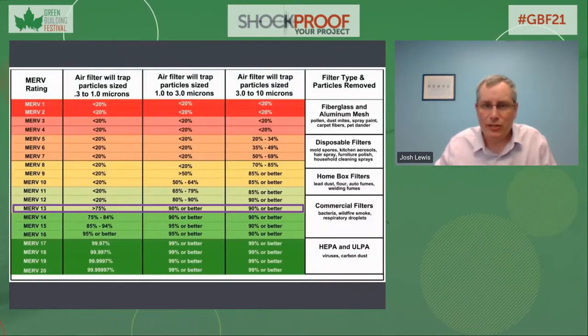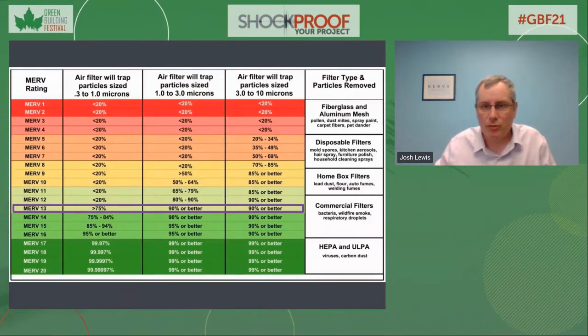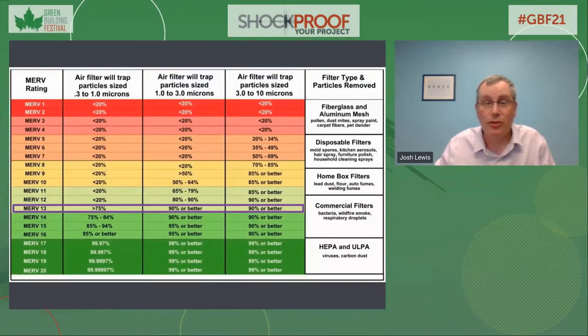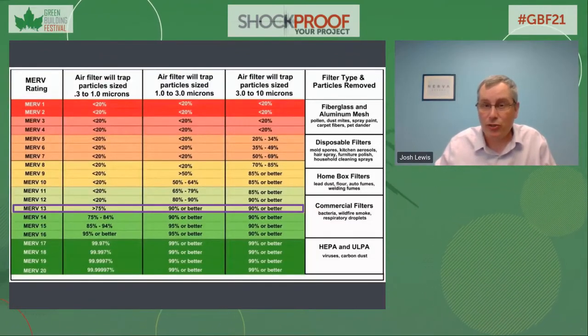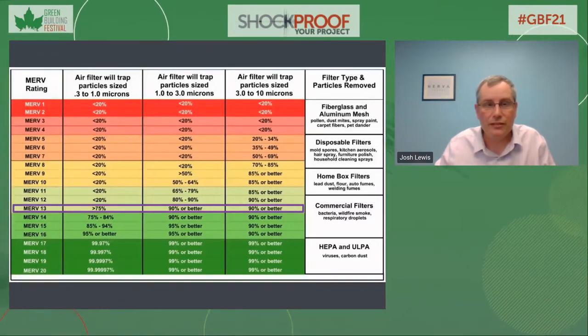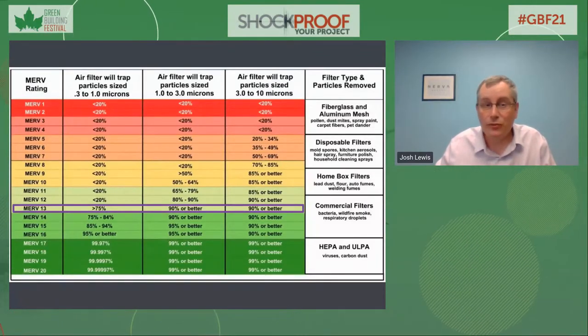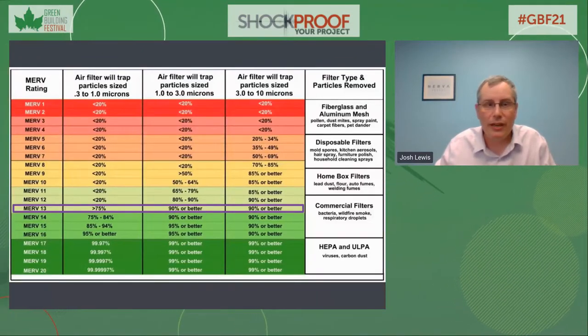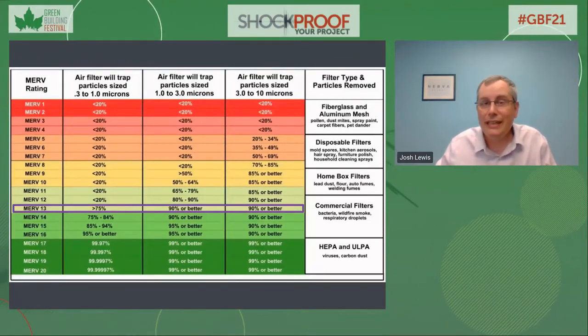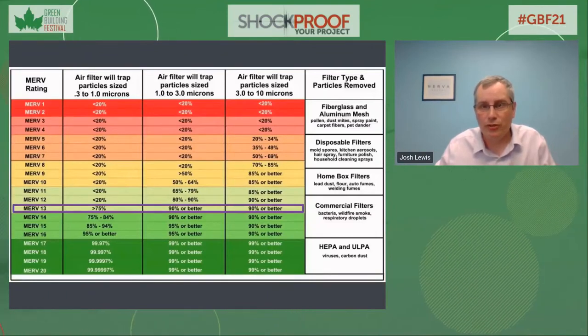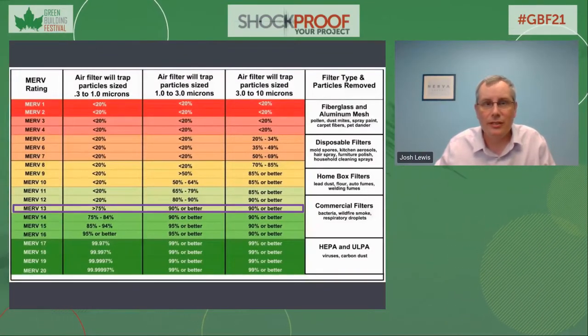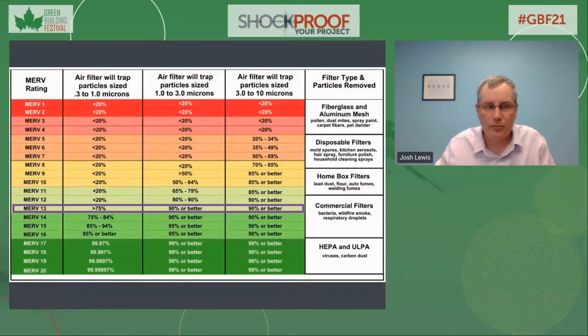The impact of both of these concerns can be minimized by using a measurement, specifically the differential pressure drop across the filter. The amount of pressure lost across the filter provides a clear indication of how dirty the filter is, and also how much impact it's having on the amount of energy the fan is using to move the air. The most energy efficient, cost-effective, and environmentally sustainable way to decide when to change a filter is to measure and monitor the differential pressure across it, then swap it out when it hits the manufacturer's recommended pressure value.